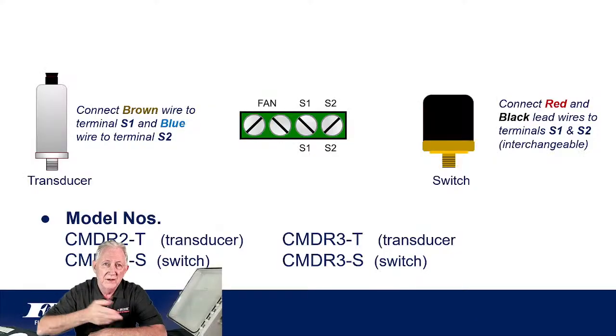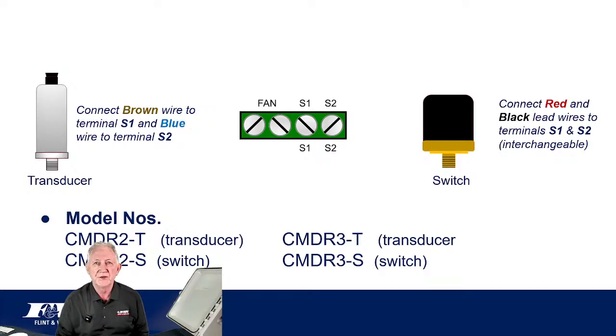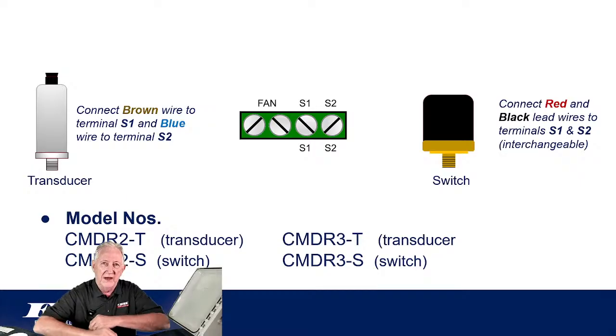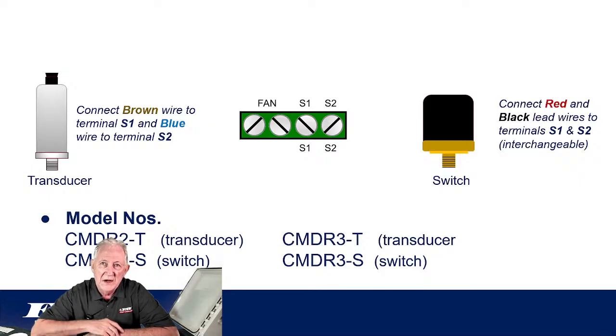So again, when we wire, if this is a transducer, and we don't want to keep any of this a secret, it's going to have 2 wires come off of it, a brown and a blue. We're going to hook the brown to that number 1, S1 terminal, and we're going to hook the blue to the one next to it, S2. It's very, very simple to do if we follow the instructions, all right? So installing this drive, there's no magic to that. It's just a matter of wiring, and everything's well labeled and well marked.